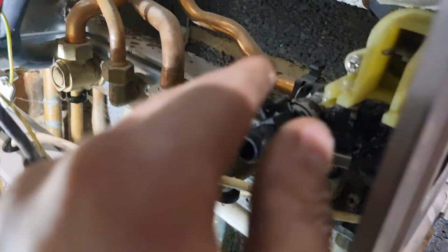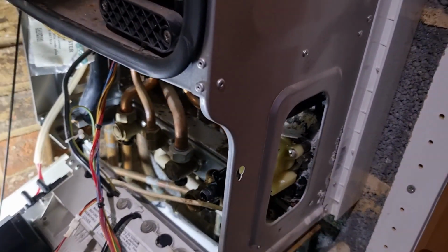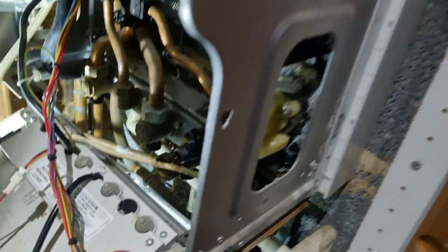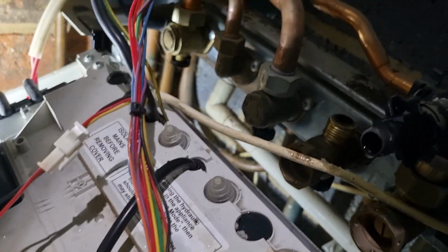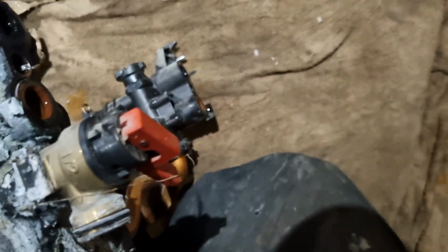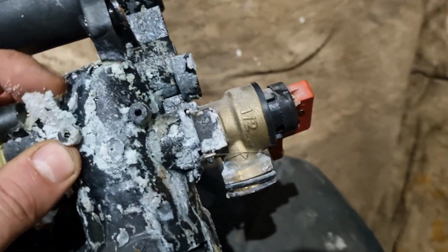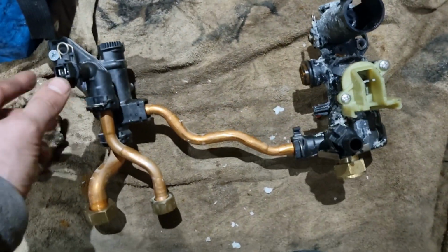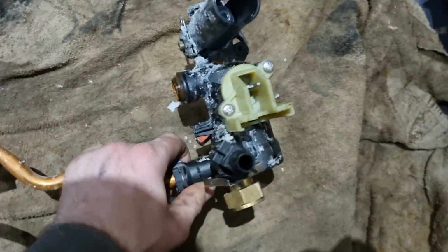Just a leaky Worcester. I'm going to change the left-hand side, right-hand side, flow turbine and PRV on this one. And I've already pumped the expansion. So we'll get this one done. I think that one has been leaking a while. They normally crack around here somewhere, but I'll change it all anyway. Change the left hand side because it's a cheap part and it makes it easier anyway.